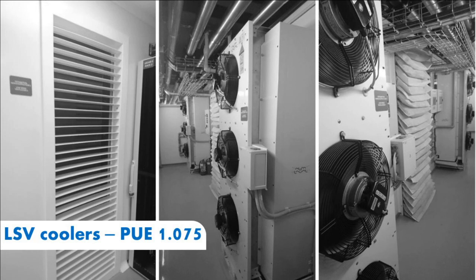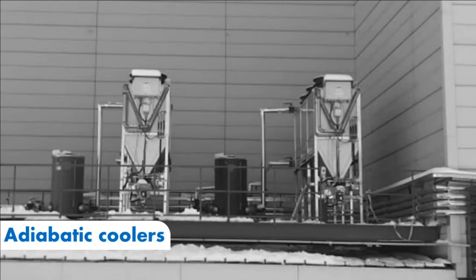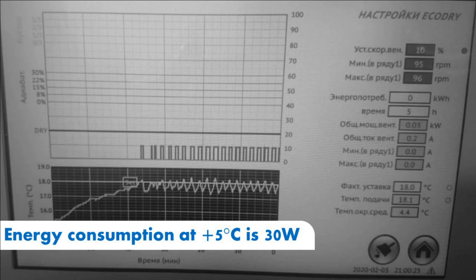Each low-speed ventilation cooler has a rated capacity of 40 kilowatts with an energy consumption of 500 watts. And in general, the system has an average annual PUE of 1.075 and a maximum design temperature of plus 43 degrees. Innovative adiabatic coolers allow you to work 85% of the time in a year in dry mode, and the rest of the time use a minimal amount of water without water treatment. The test at maximum load showed the consumption of adiabatic coolers at an ambient temperature of plus 5 degrees was only 30 watts due to a large heat transfer area. Today, many data centers at plus 5 begin to turn on the chiller for cooling.